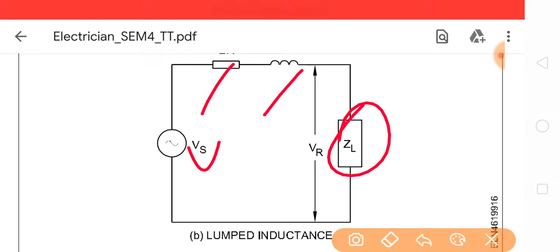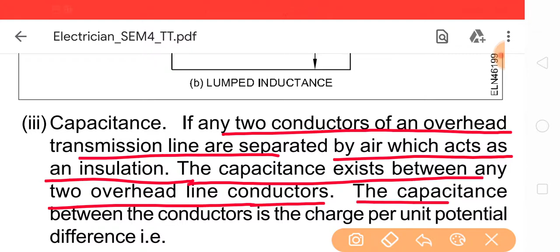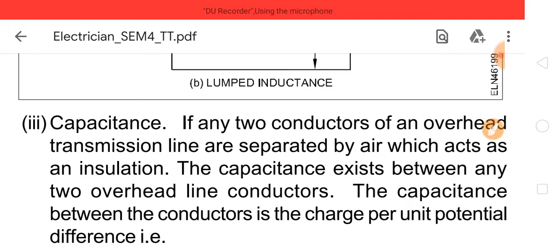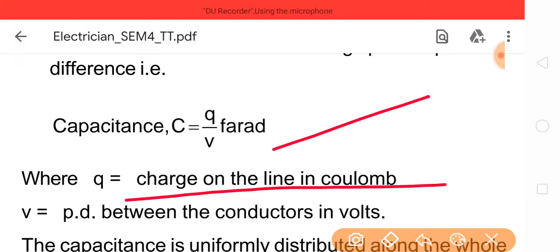Capacitance: if any two conductors of an overhead transmission line are separated by air, which acts as insulation, capacitance exists between any two overhead line conductors. The capacitance between conductors is the charge per unit potential difference, i.e. capacitance C = Q / V Farad, where Q is the charge on the line in coulombs, and V is the PD between the conductors in volts. The capacitance is uniformly distributed along the whole length of the line and may be regarded as a number of capacitors connected between the conductors as in picture 7a.